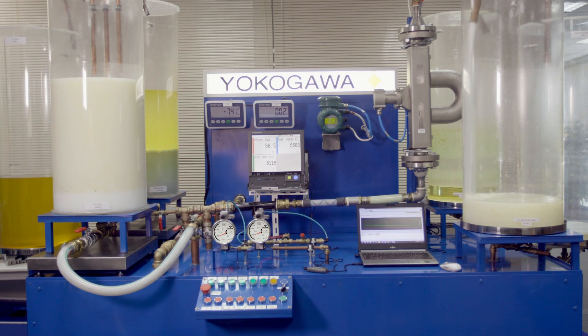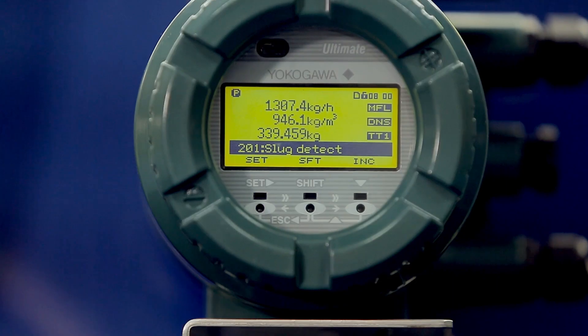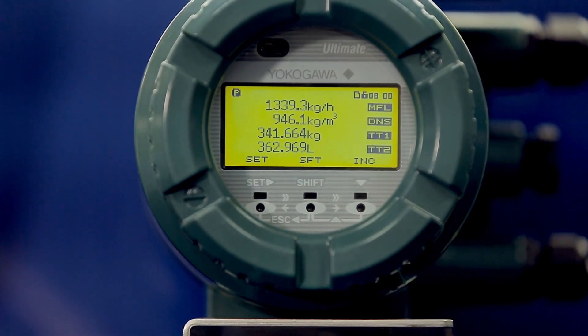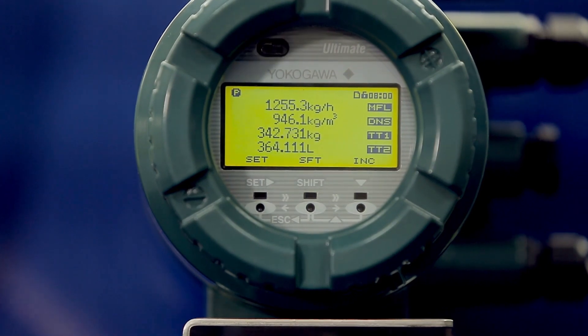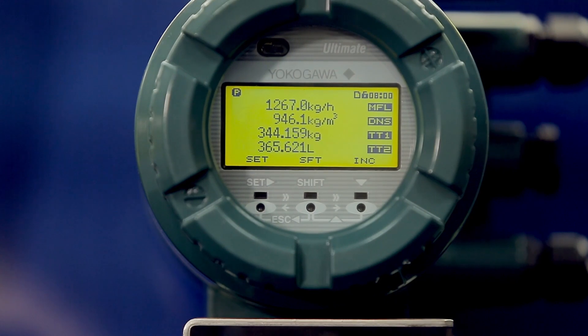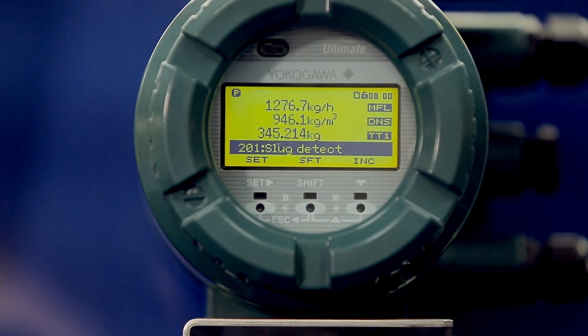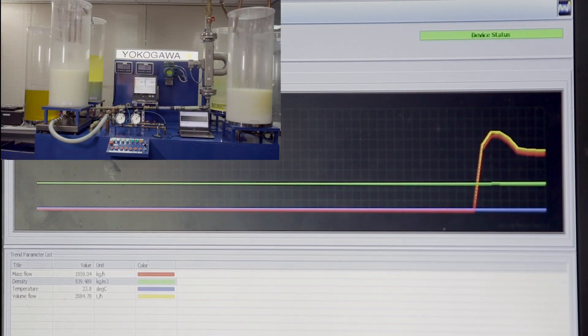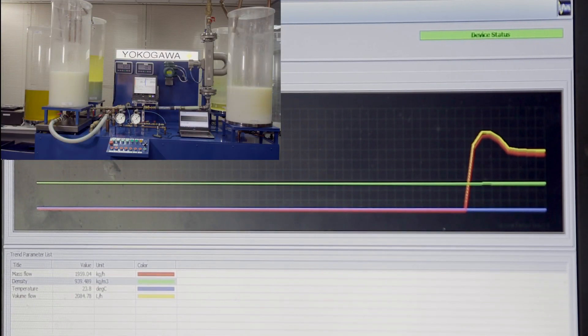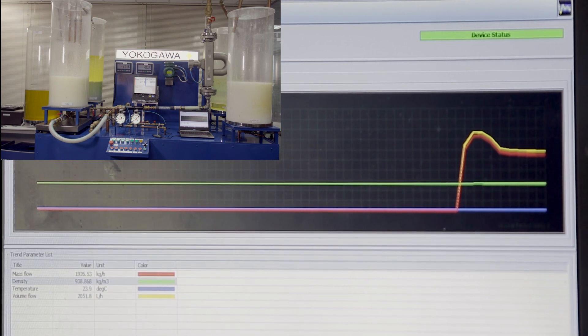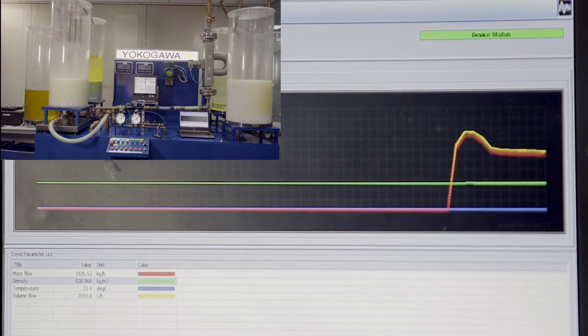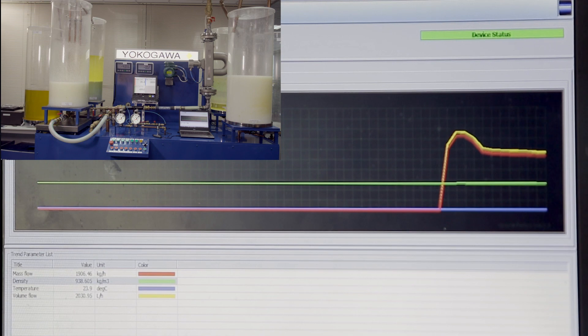The Rotamass is measuring the water cut percentage, net oil flow, and gross flow. We can see the Rotamass display a slug detection alarm when it detects entrained gas in the process. The Rotamass continues to measure accurately and repeatably despite 25% air entrainment — the meter does not stall or freeze the last measured value. The graph shows live process data: density in the green plotline, mass flow in the red plotline, and volume flow in the yellow plotline. The computed density by the advanced net oil computation algorithm is accurate and constant even with 25% entrained gas present continuously.